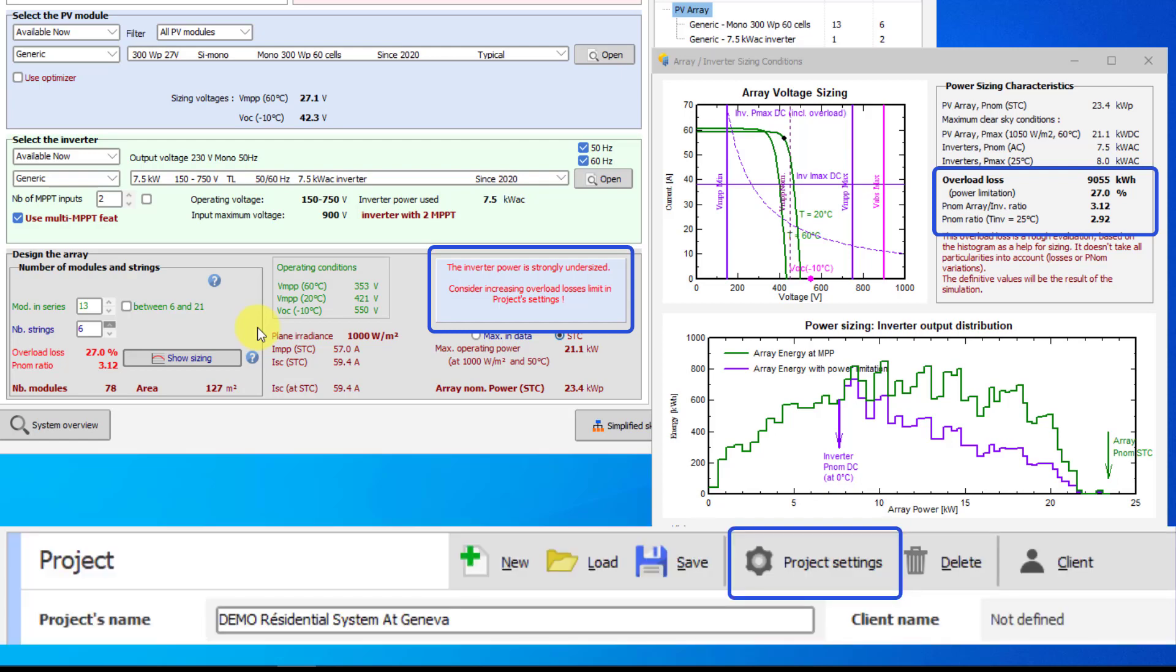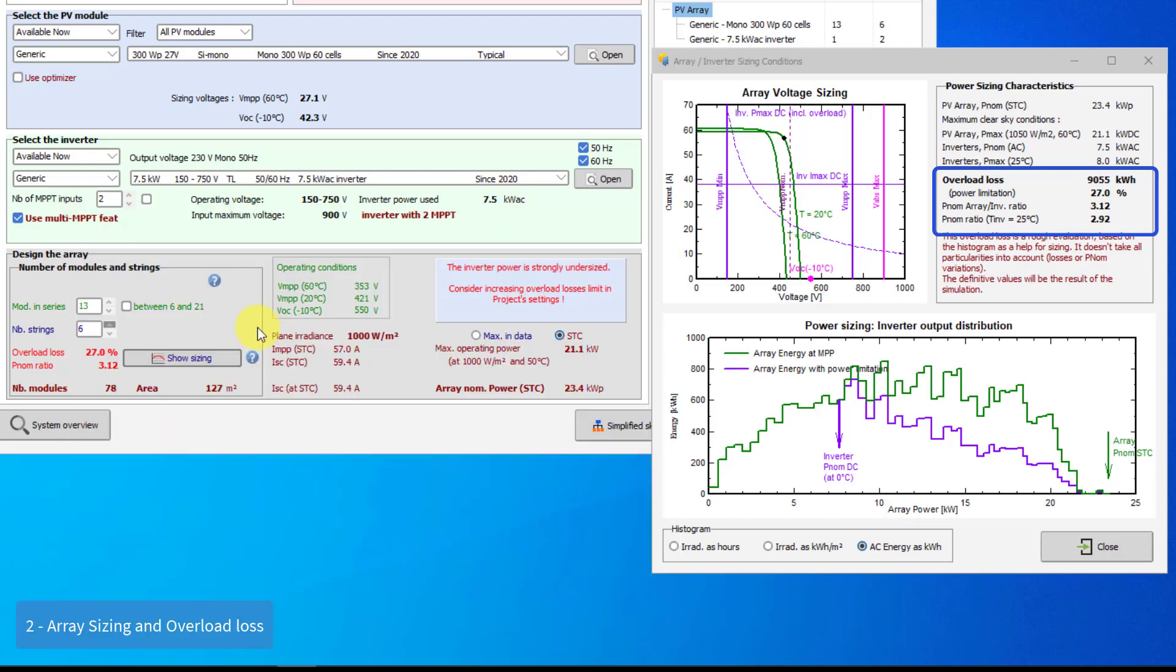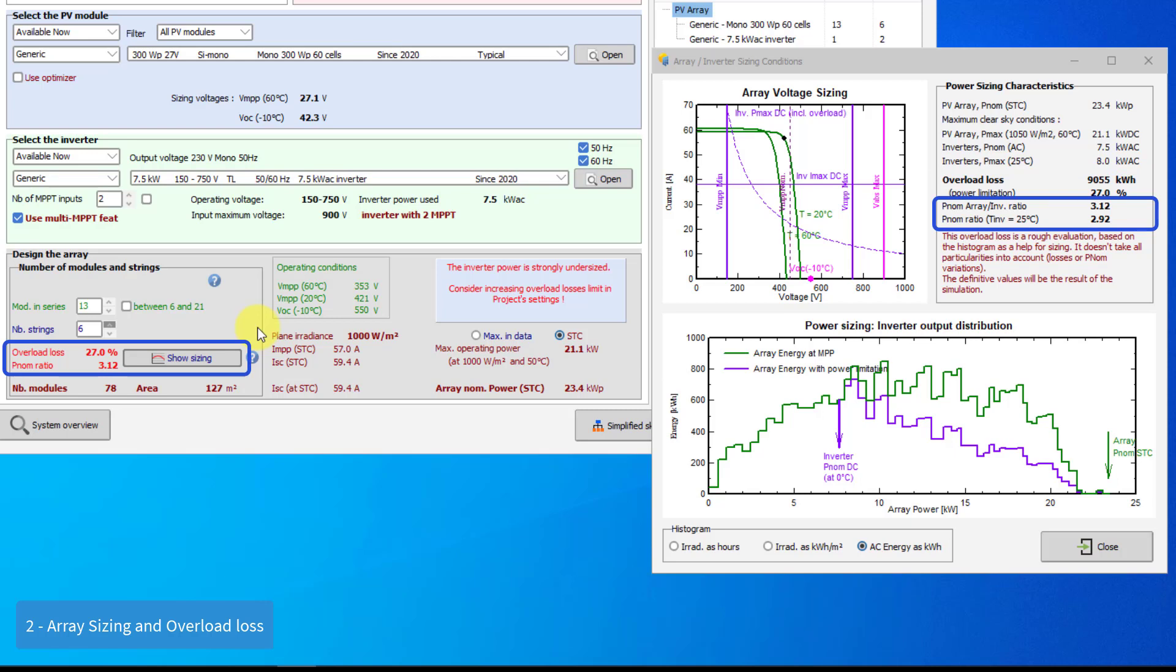An important indicator is the nominal power or PNOM ratio. This is often called the DC-AC ratio. A good sizing usually corresponds to a PNOM ratio of between 1.25 and 1.3.